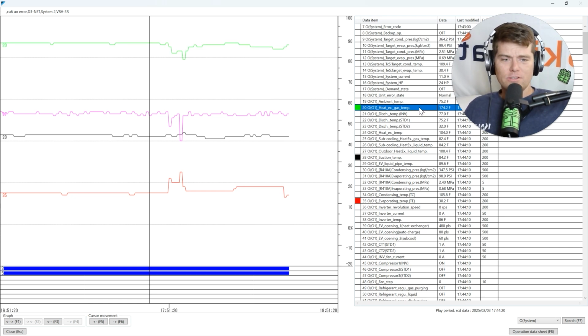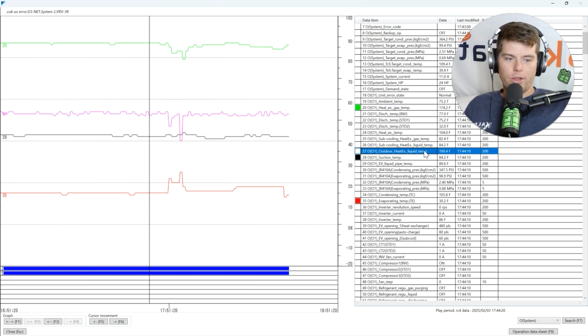Why is that important? Because if I'm taking subcooling on a module where no refrigerant's actually flowing through the coil, guess what? Subcooling's pretty high. And it's not. Discharge superheat's high, suction superheat's high. Now let me do the subcooling on the actual module that has actual liquid flowing through it, and that's right here. 100 degrees with 100 degrees and 105, that is a 5-degree subcooling.